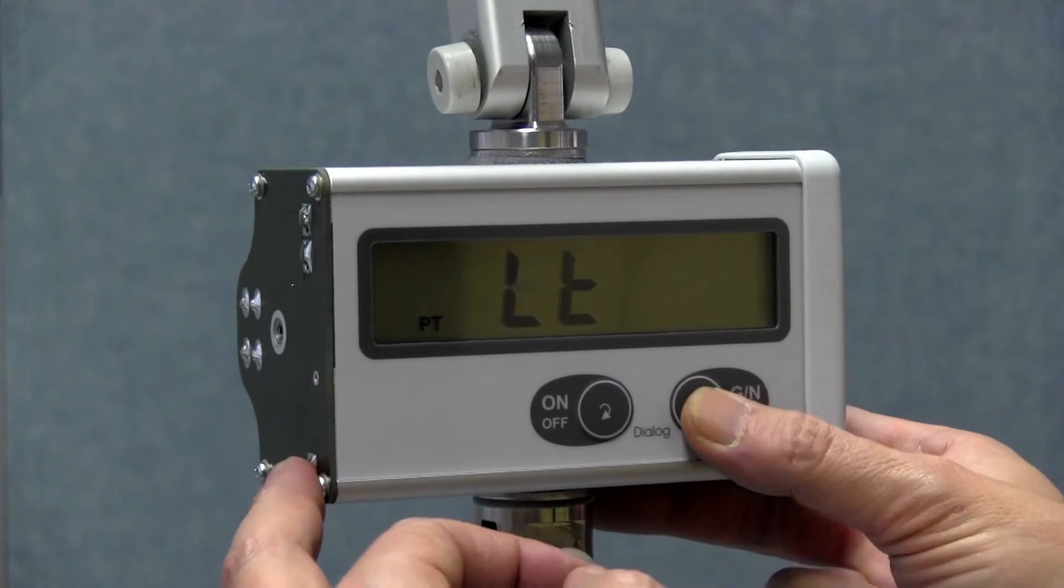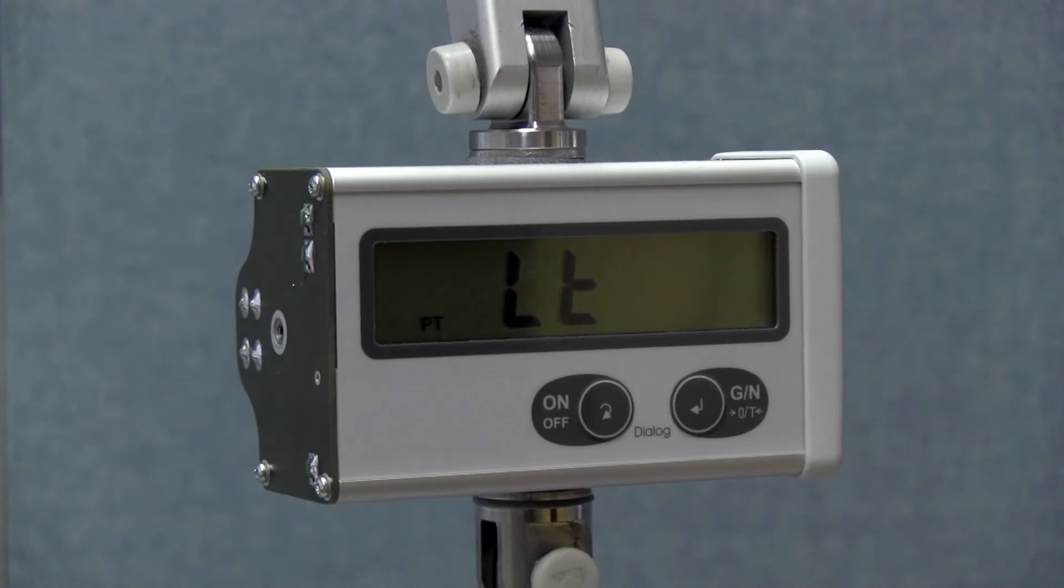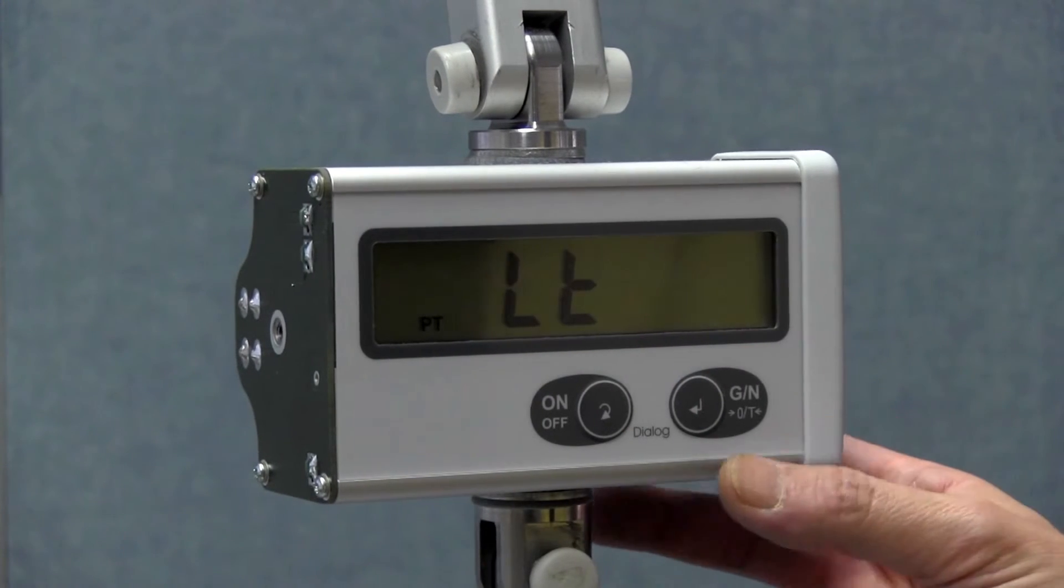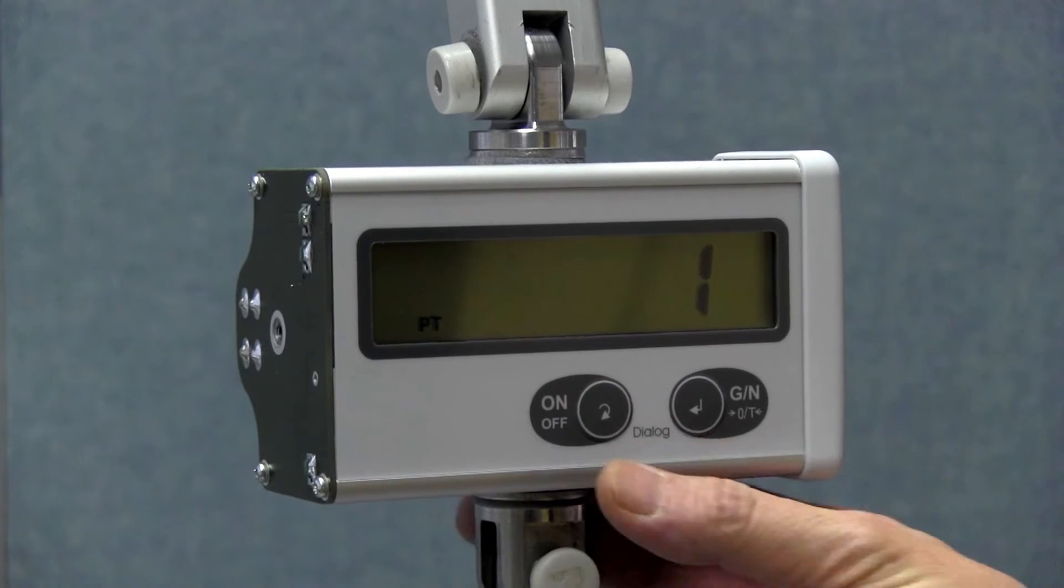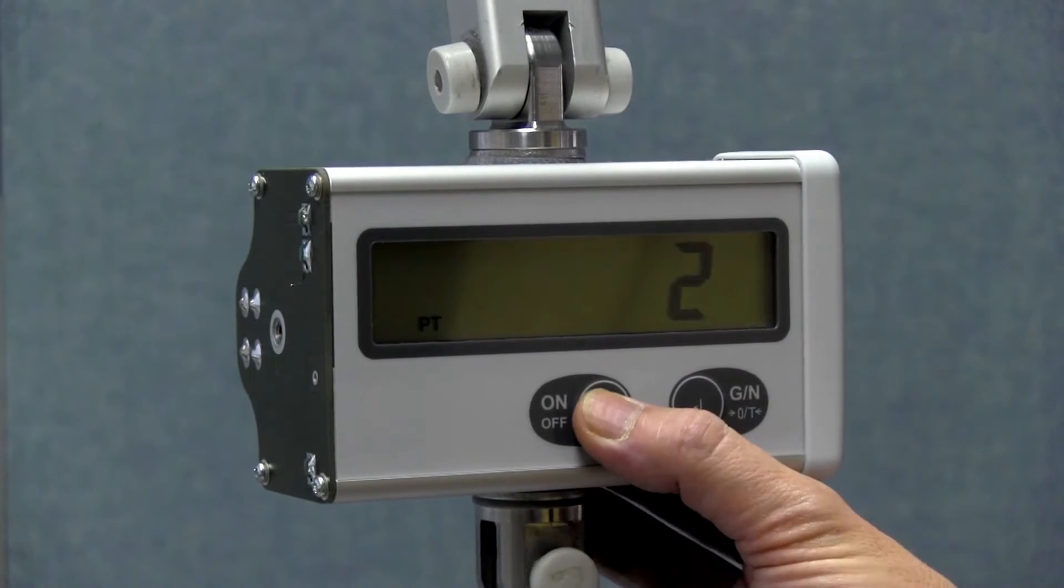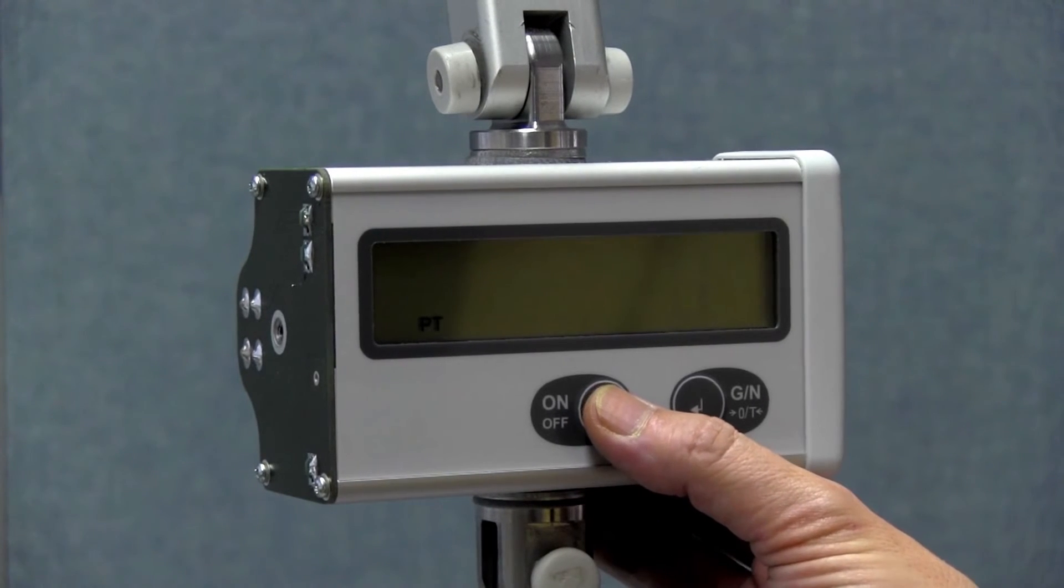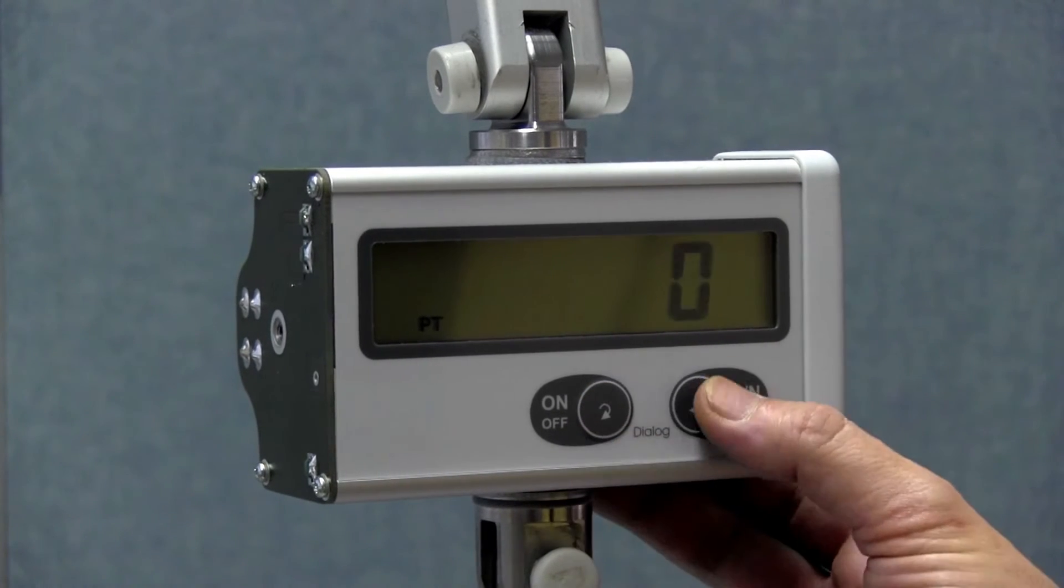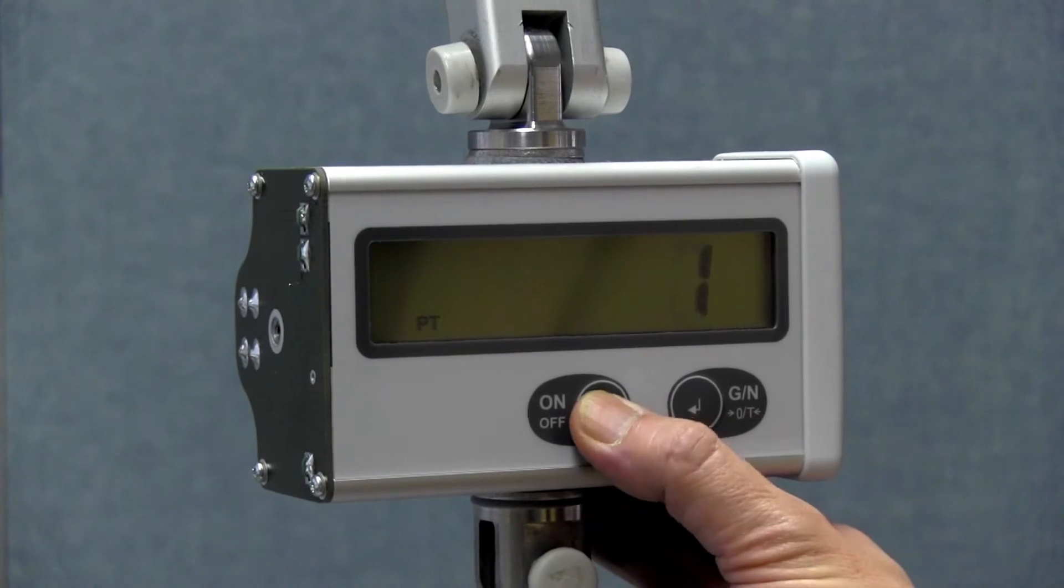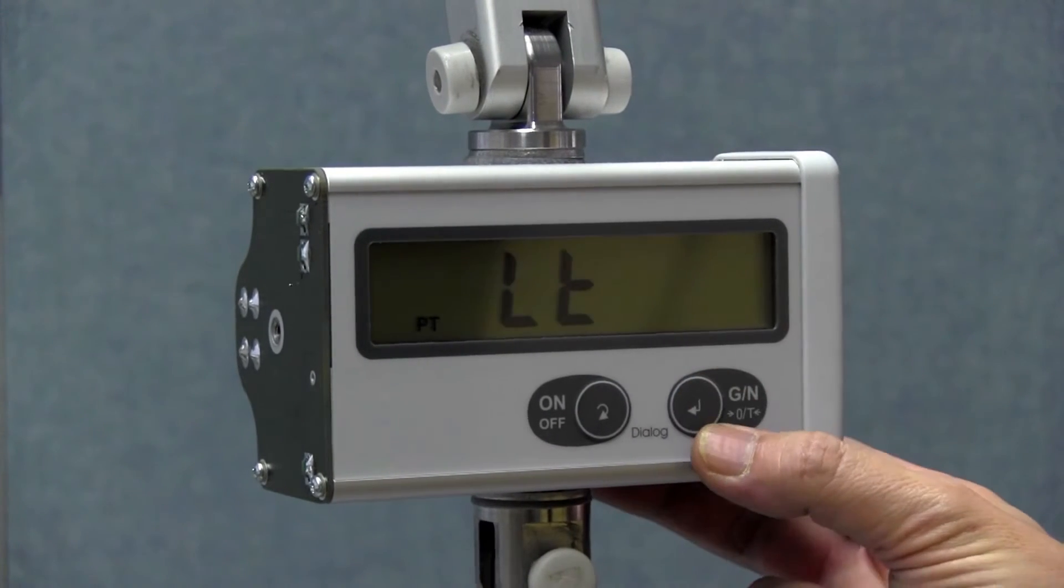The next query item for calibration in a partial load range is legal for trade. Am I in a legal for trade or not legal for trade mode of the scale? The sling scale permits three selection criteria. Zero for not turned on, one for OIML, and two for NTEP, which indicates legal for trade capability in the USA. I select one for OIML, and confirm with the GN key.